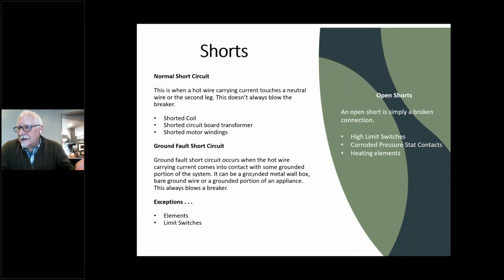You can also have corroded pressure stat contacts, for example. Even though they're coming together, they're not actually making contact. So in a sense, that's an open short. So you have cases where wires are touching things that they shouldn't, and you have cases where wires aren't touching things that they should. The only couple of exceptions, for example, on elements: an element can be fractured inside and will actually leak voltage to ground through the water inside the boiler, and it won't blow the circuit breaker. It's doing that because the water itself is becoming a heating element, and it's referencing ground. So essentially a 240 volt element now becomes a 110 volt element, but with massive resistance. In that case, the boiler will actually get warm, but it won't get hot. And because it thinks it's just trying to heat up the water, it's not enough to blow the element.